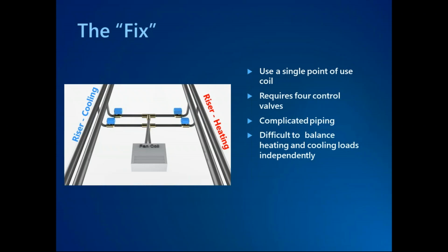Now the solution works, but it has 4 control valves, which means 4 points of communication back to your building management system, 4 points of failure. On top of that, when it comes to sizing and designing, 2 of these control valves, typically the ones on the supply side, are going to be just on-off without any pressure drop consideration, no CV calculations, whereas the 2 control valves on the return side are often going to be designed to be modulating control with the CV calculations associated with it. So from a scheduling and coordination standpoint, it can be very difficult to make sure everything goes off without a hitch when using this type of design.